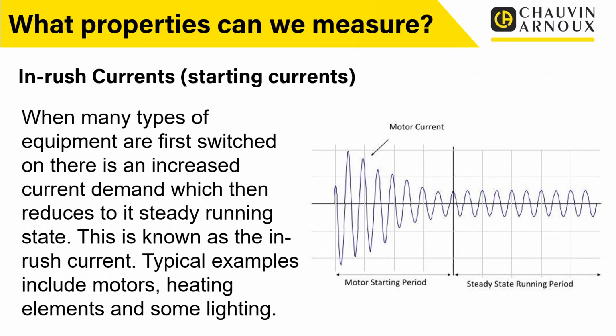Now, the problem with this is that we need to make sure that, for example, the circuit breakers that we've used don't operate because they see this high starting current. But also, we don't want circuit breakers that are set way too high for the normal operating current, because under normal operating conditions, we want it to still detect a fault. So understanding these inrush currents, understanding where they come from, and then designing the protective devices, the conductors, the switchgear, and motor drives, all those sort of things, to account for this is very, very important.